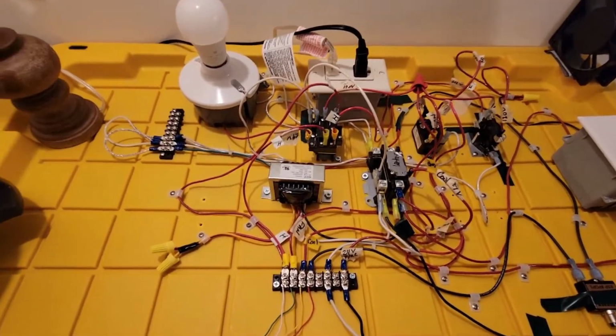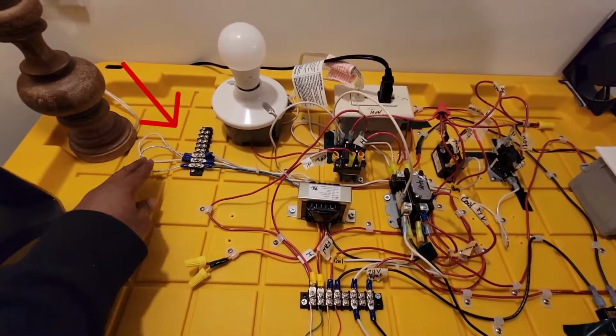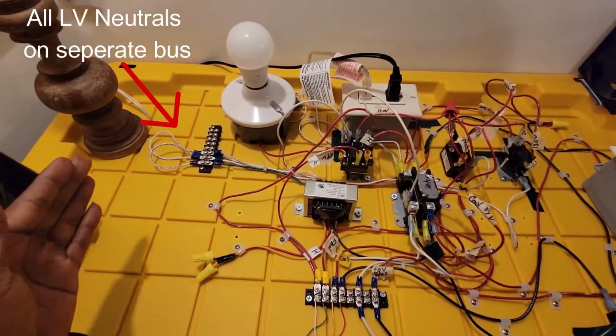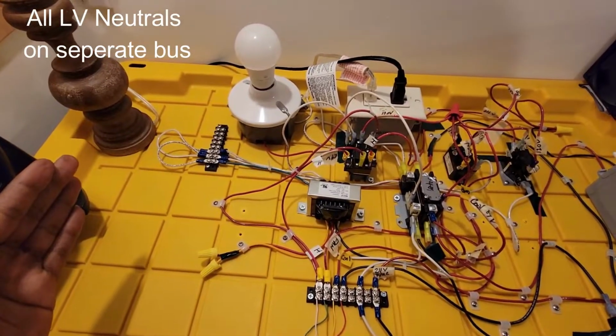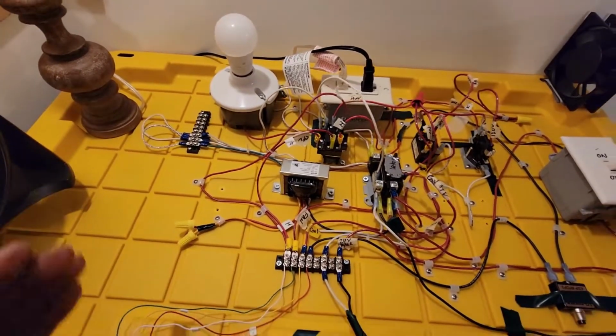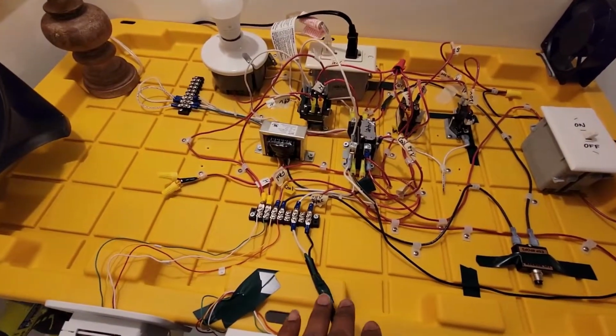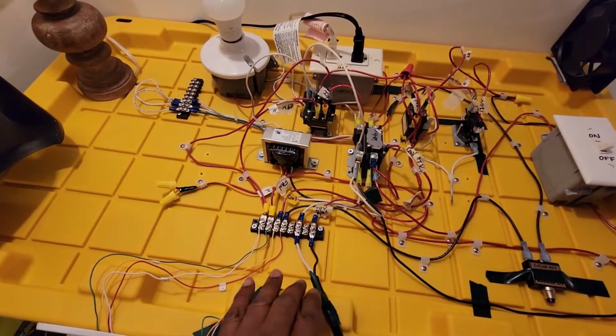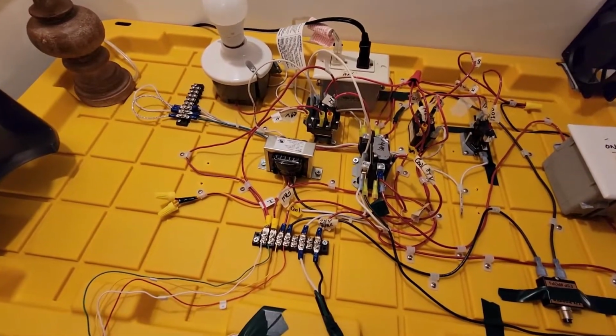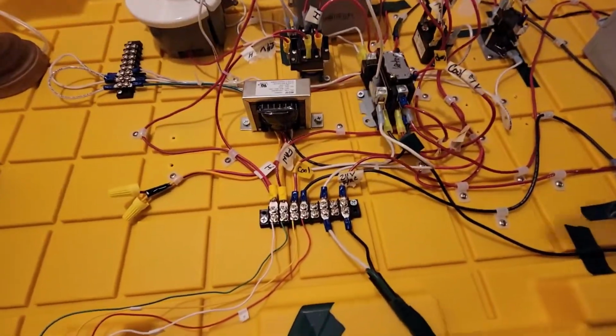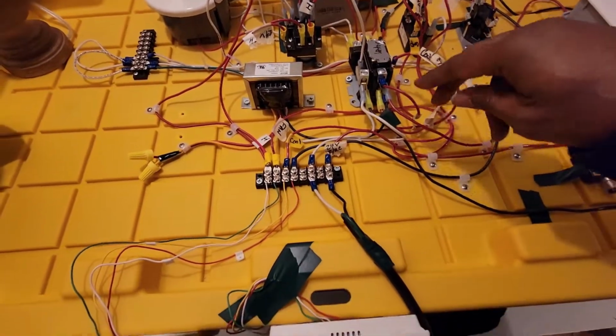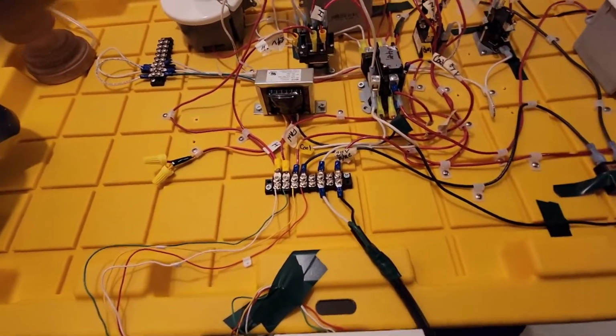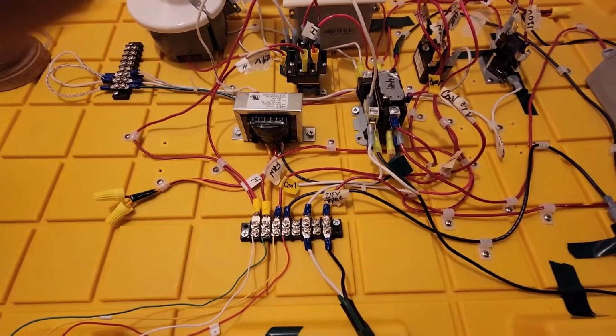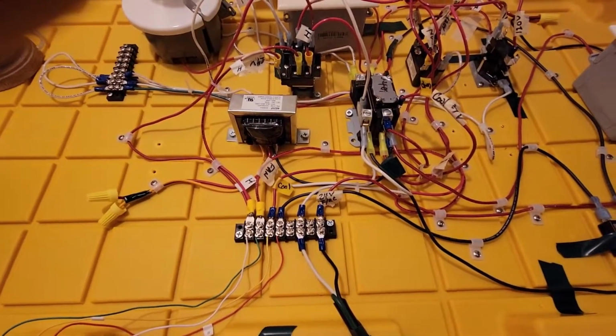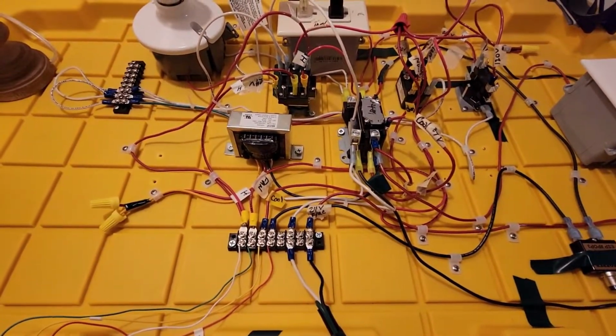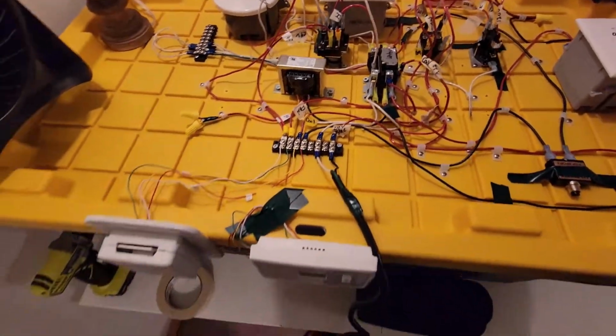And so I have my neutral bus. This is my low voltage neutral bus. You have to separate all of your low voltage neutrals from your high voltage neutral, and that's what I've done over here. So I have high voltage neutral, just one line right here, and it's going to the contactor, and all those high voltage neutrals are coming from that contactor connected to our system. And I think that's pretty much it.